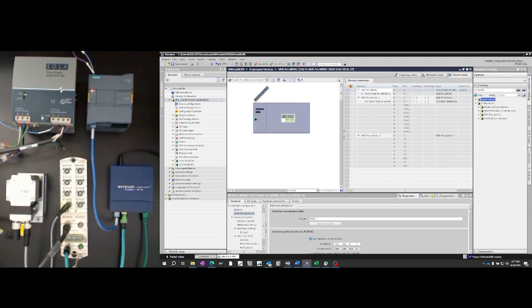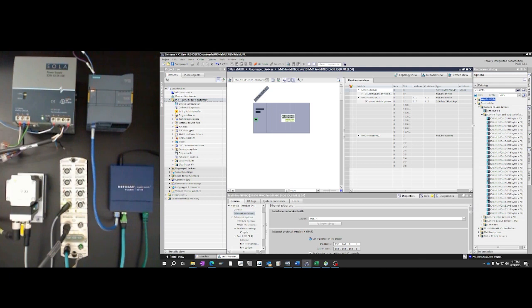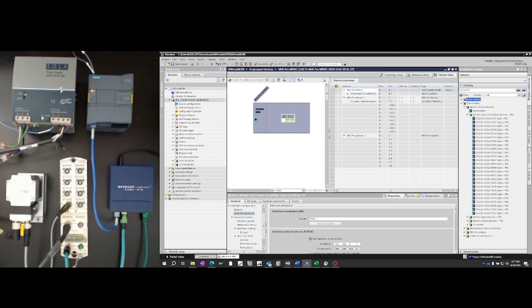Underneath submodules, you'll click Generic IO-Link Devices, Generic Input and Output Devices plus a PQI byte. And the closest thing to our device is going to be 2 bytes in, 2 bytes out, plus a PQI byte. Click and drag that to slot X0.